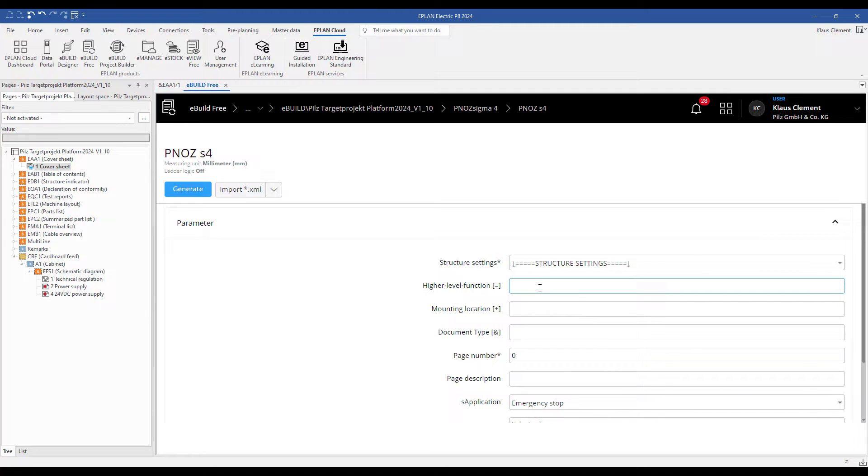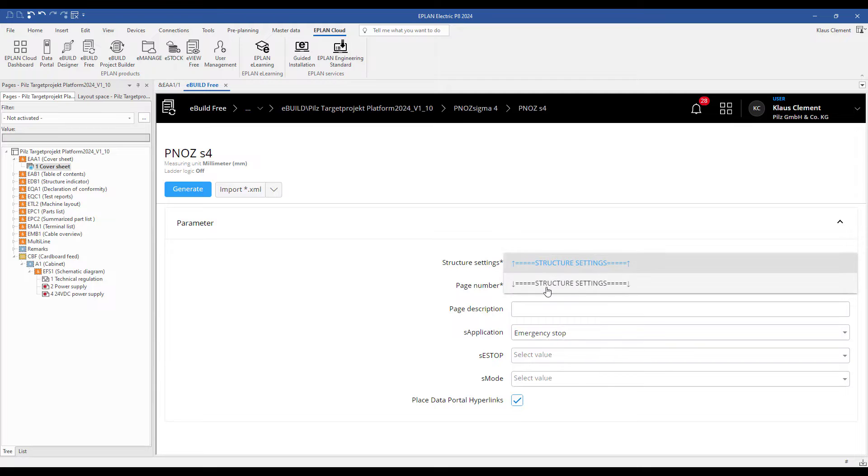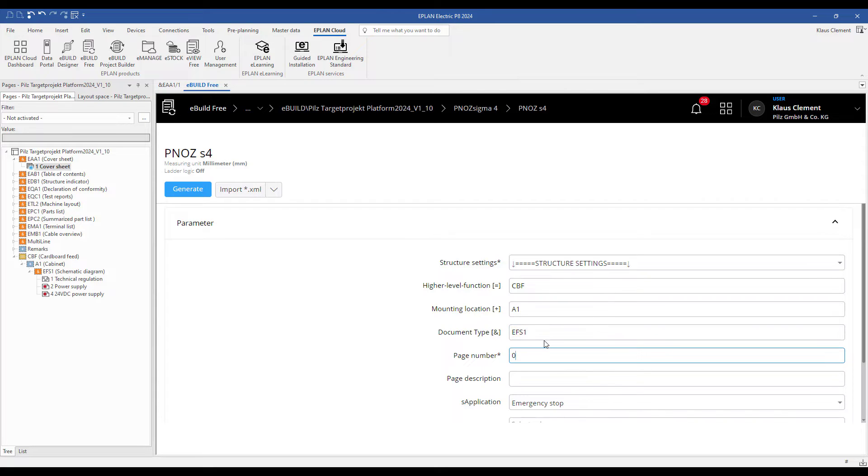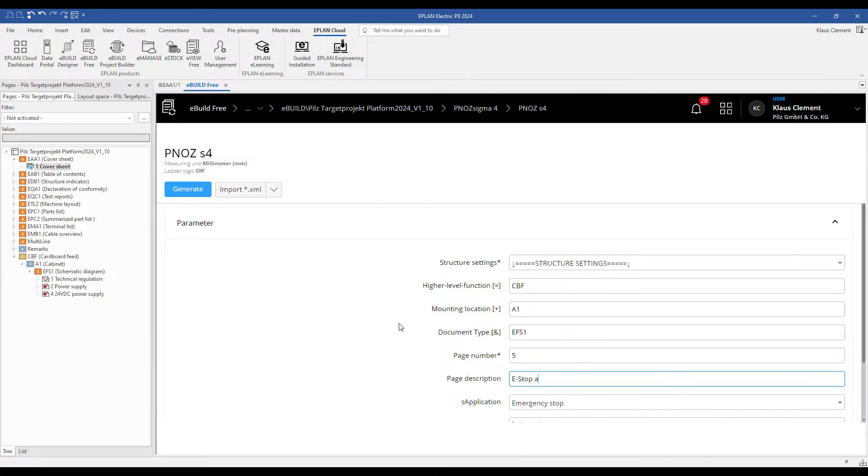I fill out the page settings according to IEC 81346. High level function CBF, mounting location A1, document type EFS1, page number 5, page description E-Stop and SafetyGate application.